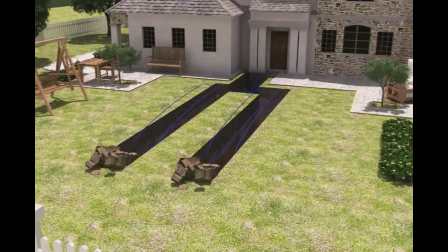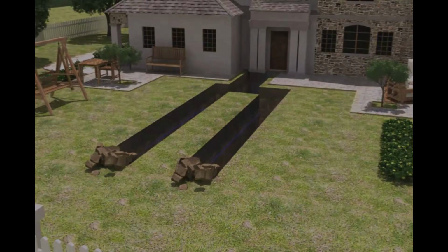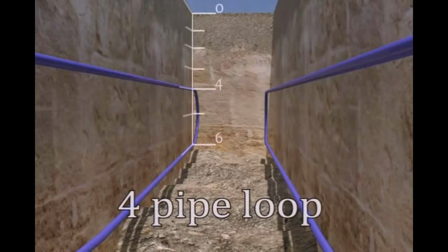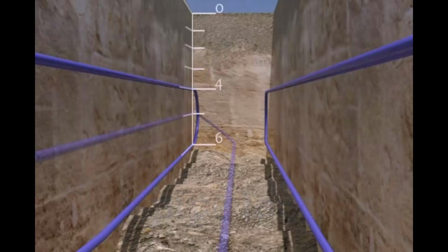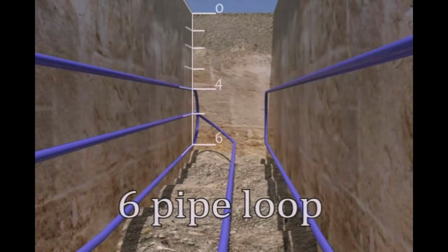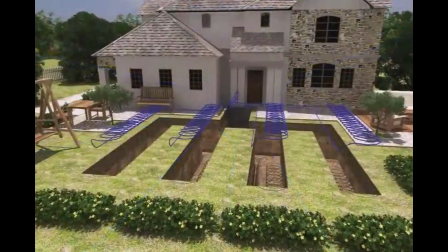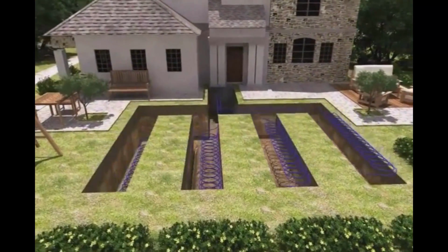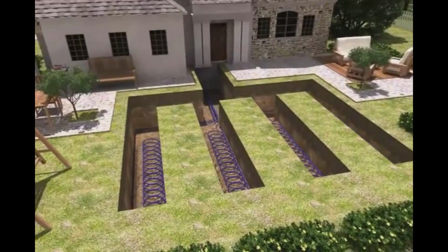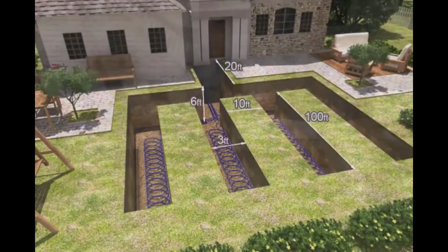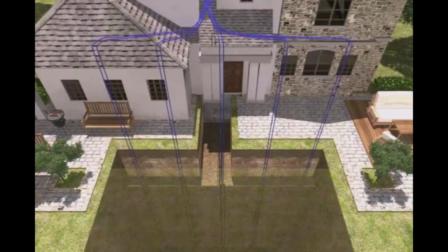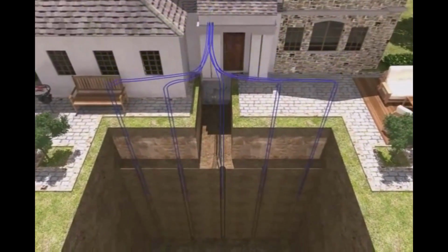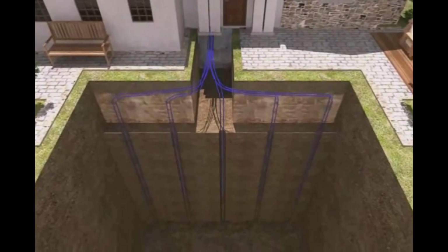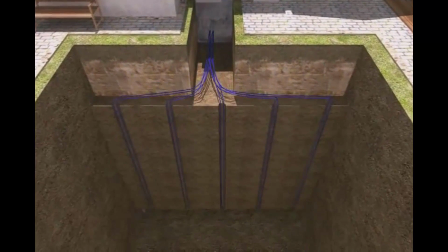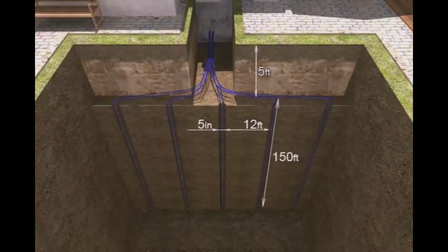The loop is placed in the excavated ditch. This example demonstrates how a 4-pipe and 6-pipe horizontal loop will be placed in the excavated ditch. A slinky loop is used when land space is restricted. In this example, we used 100 lineal foot trenches to provide enough length for the system to be energy efficient. A vertical loop is used when the required space for horizontal trenches cannot be achieved. Approximately 6-inch holes are drilled and loops are installed and grouted.